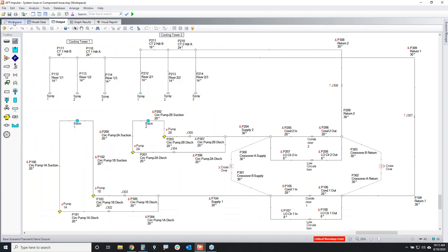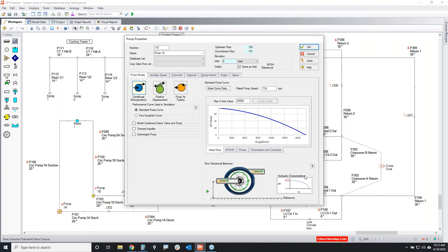here's my pump curve. And when you have flow rates that are less than zero and they go negative, what's the pump head? Well, we don't know. So what we're going to do is impose a fixed pump head of the shutoff value, which is about 80 feet. That's the shutoff head for these particular pumps. How can I confirm that?